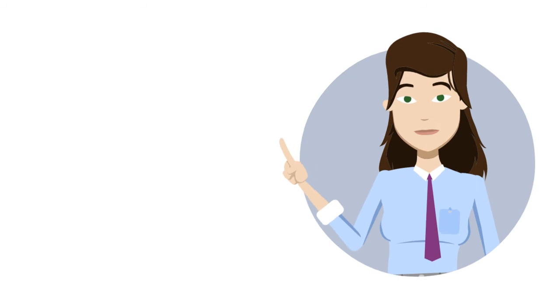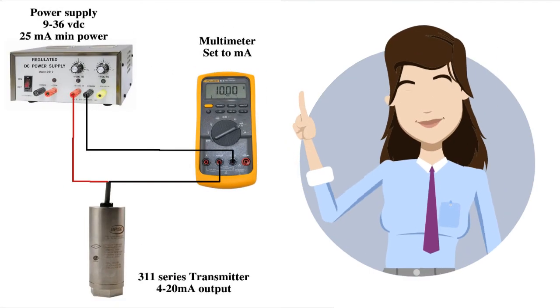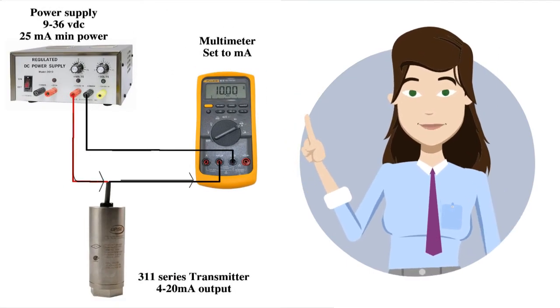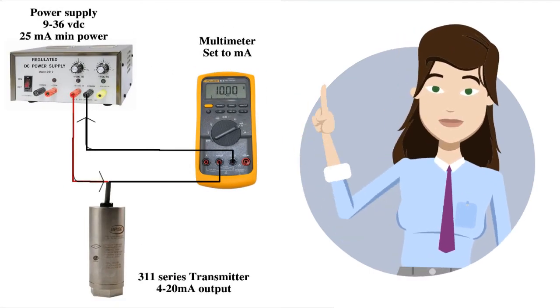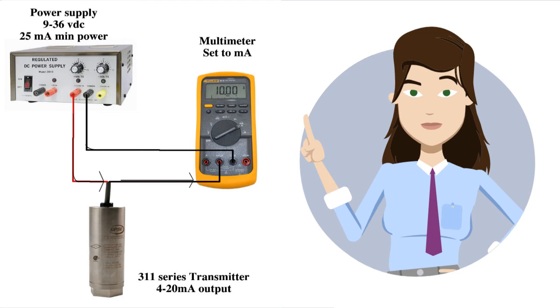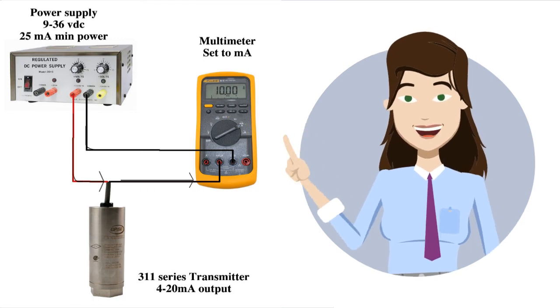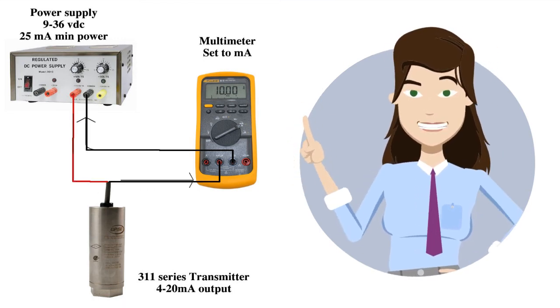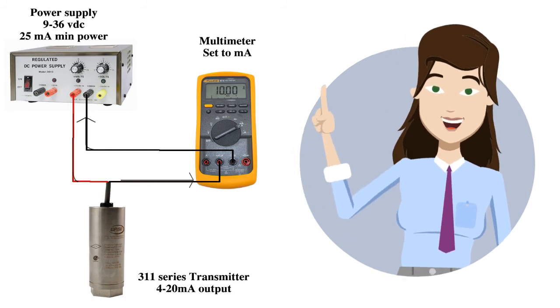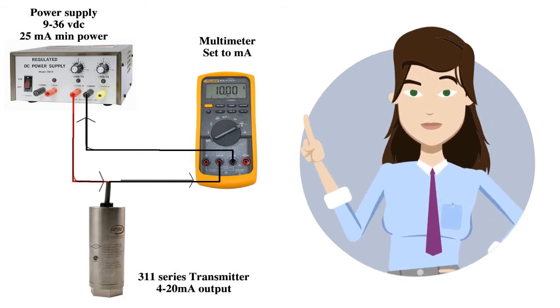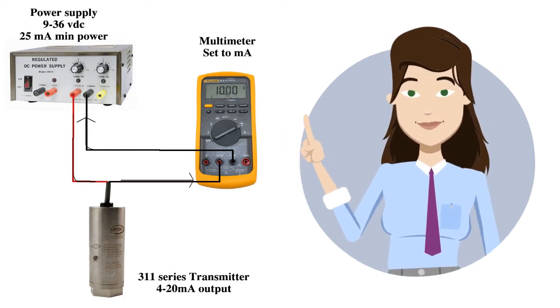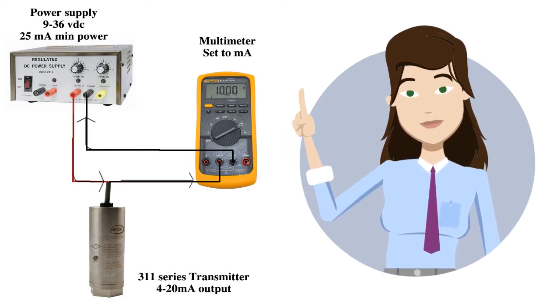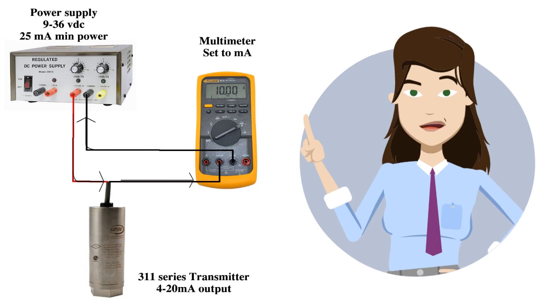You have now completed the milliamp loop hookup. The milliamp signal runs from the power supply through the pressure transmitter, back to the multimeter, then loops back through the return side of the power supply. The transmitter acts as a current limiter — the more pressure applied, the more current it allows to flow through the loop.